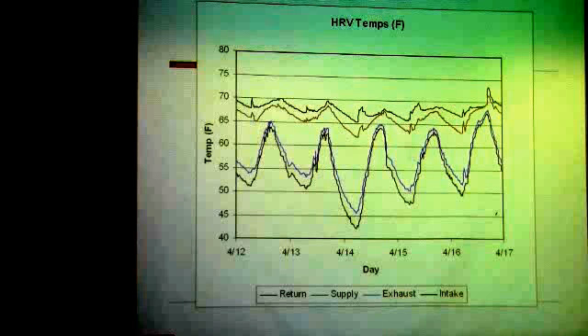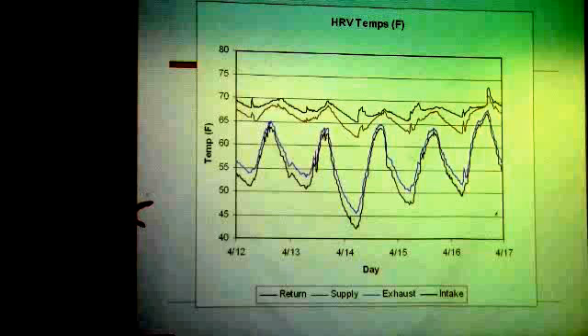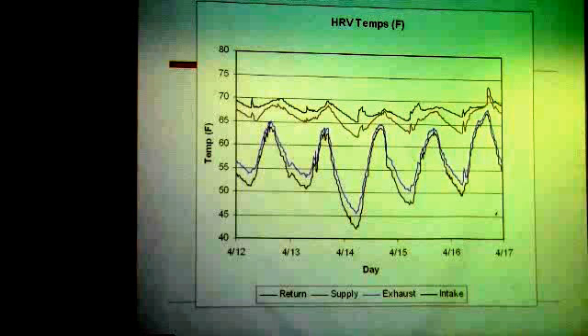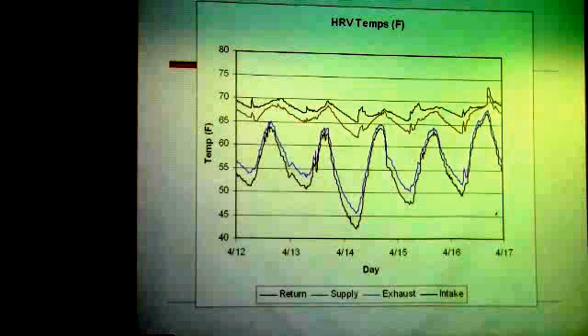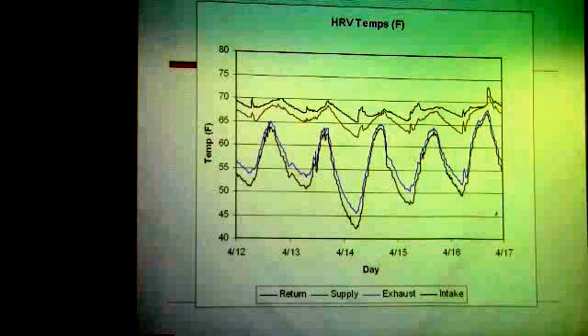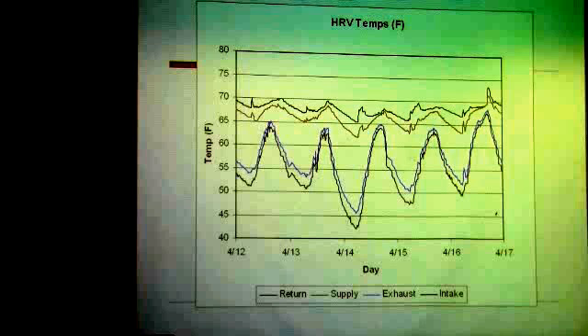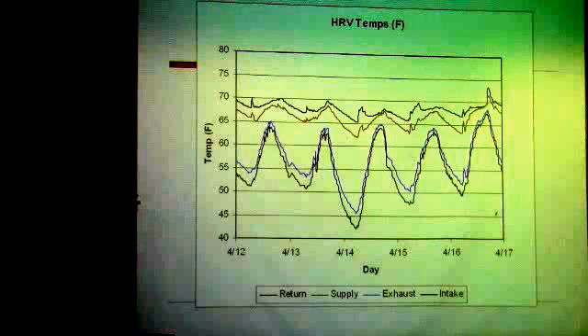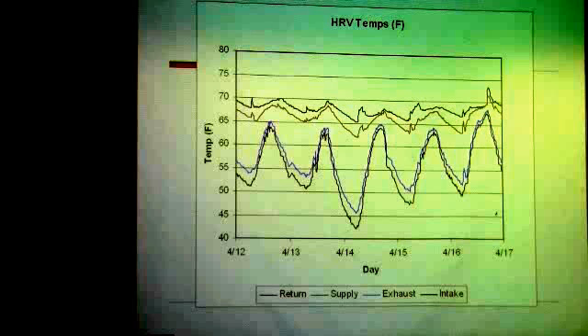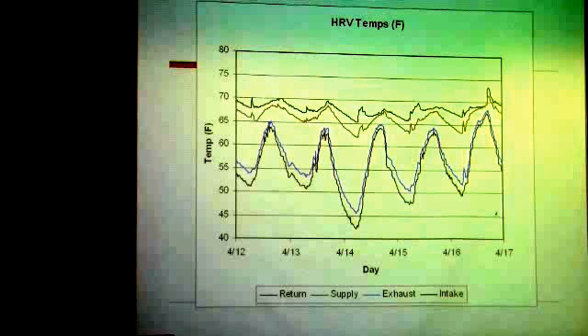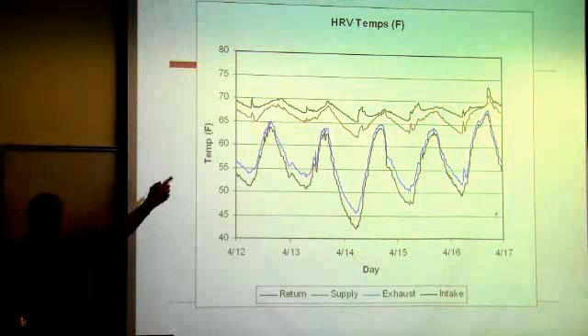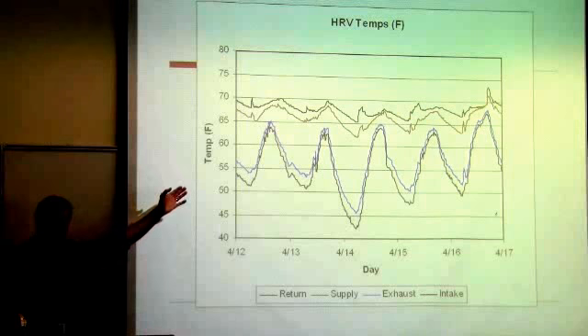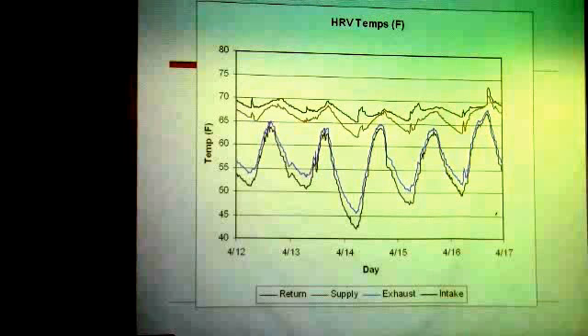So as you see, it's giving up the same amount of temperature, where the exhaust temperature is cooling down to within 2 to 3 degrees of outside temperature, and that same heat is being added on the inside. So the supply air is being increased from outside temperature to within 2 to 3 degrees of room temperature. If it was 100% efficient, the 2 lines would be the same. It would gather all the temperature.